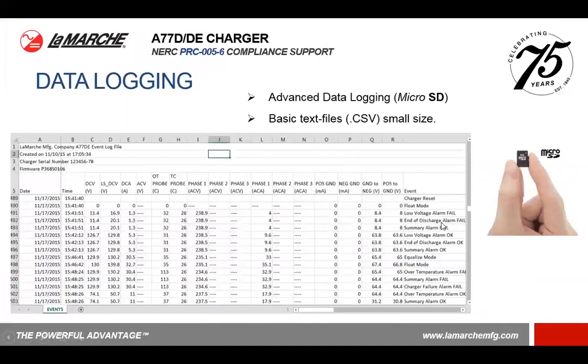We record the data locally on a micro SD card. It's a very basic text file. It's a mixture of periodic and an event-based data log. By doing that, we have a time date stamp of what the voltage is or was at that period of time, the current, the temperatures, input voltages, the ground detection. We can look at ground leakage. But what's important about that too is not only a periodic log that tells you what it was, but it also tells you when a failure occurs and when an alarm clears. So by having a mixture of periodic and an event-based data logger, you can tell what was happening on the DC system before the alarm had actually occurred, and you also have a time date stamp telling you when an event has cleared. This is fantastic for helping to eliminate intermittent problems.